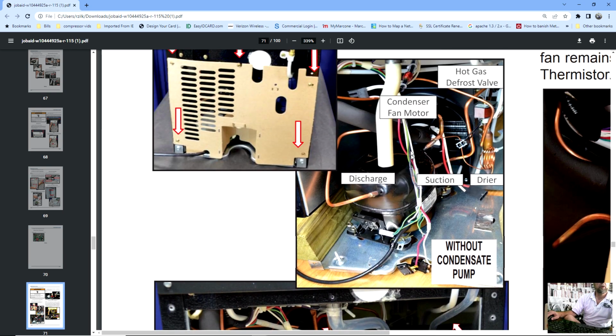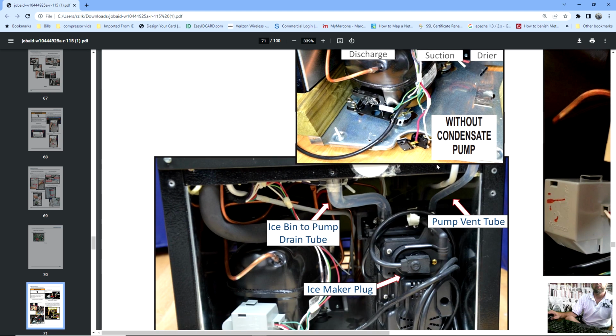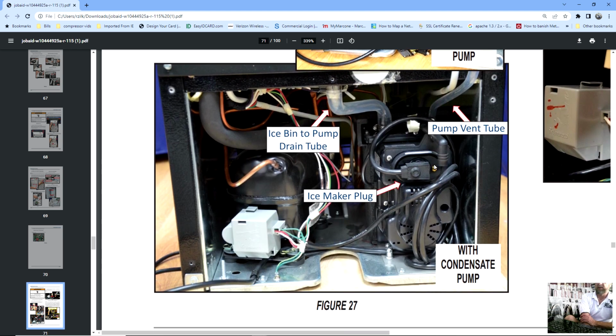And I'll explain here. If you look at this hose here, this yellowish looking hose, that's the drain hose, and the way these units are designed is that you're supposed to have a floor drain or a hole in the floor, or you could run this to another hose and run it out the back wall if the customer has the ability, like in a garage, to drill a hole through a wall and just run it into the yard out back. This is a gravity-fed drain, but if the customer, let's say, lives in a condo on the beach on the 20th floor, they don't have a floor drain in their apartment, you can add a condensate pump.